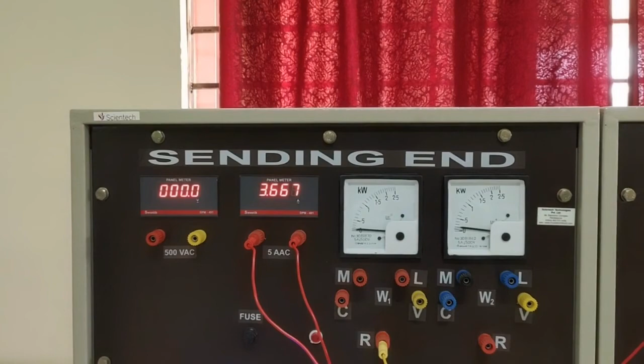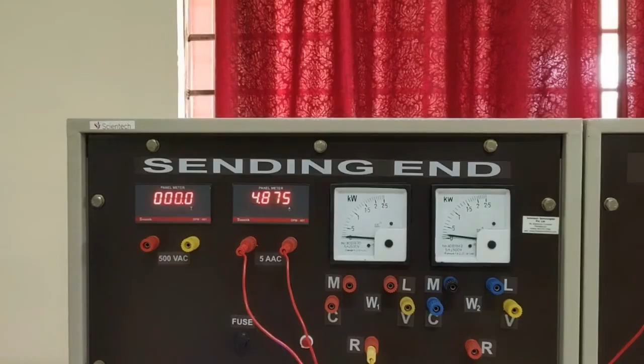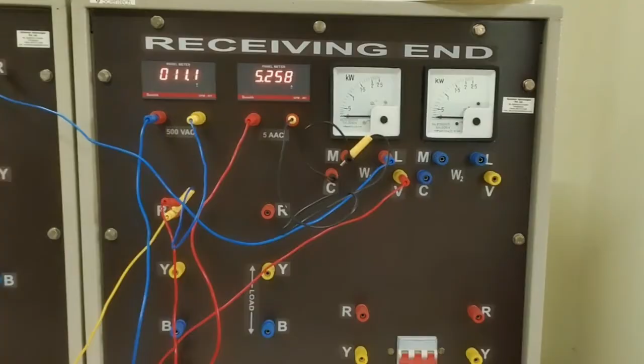Take the precautions. You can see the ammeter reading is 5 amps, the rated current, this is the short circuit current. Correspondingly, take the readings of sending and receiving end side voltmeter, ammeter, wattmeter, and short circuit current, which is 5.22 amperes.